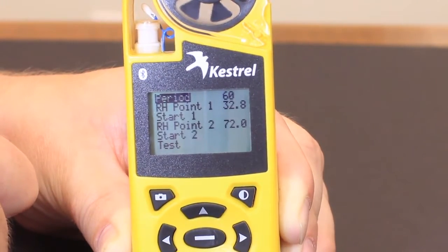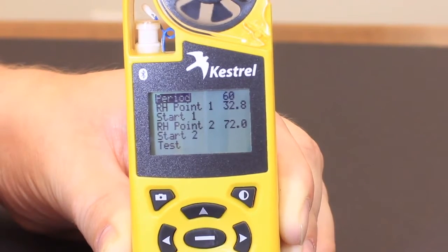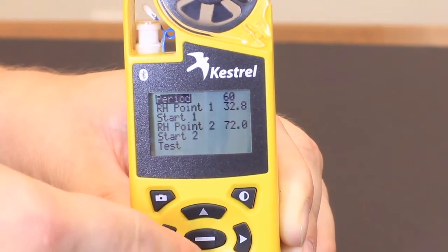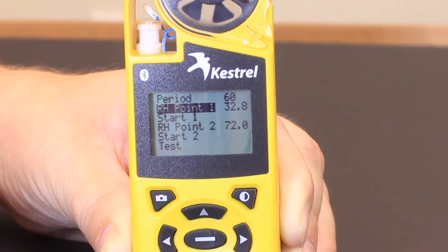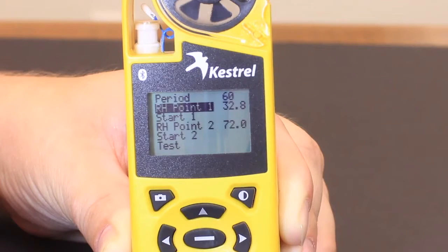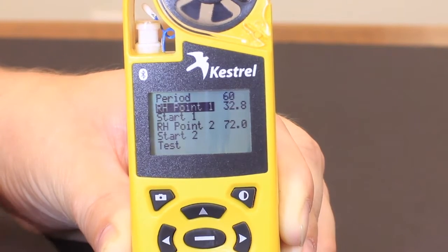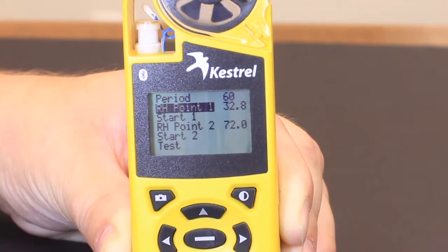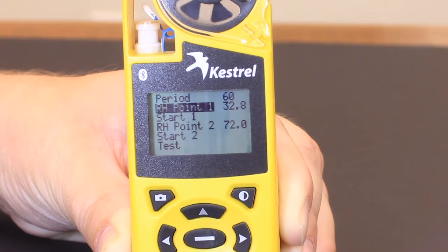You'll go down to the RH Point 1 and you want to make sure that this reads the same as the first chamber, which is 32.8 percent. Use the left and right if it doesn't to adjust this to 32.8.